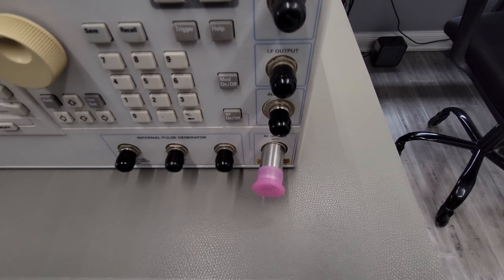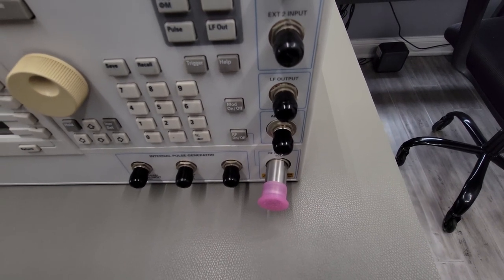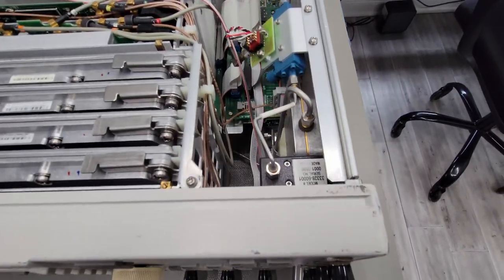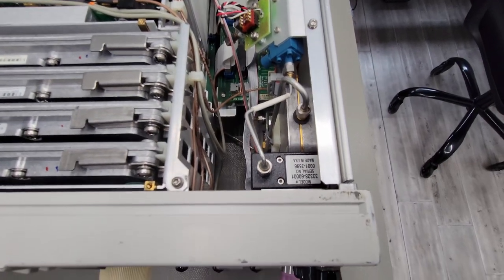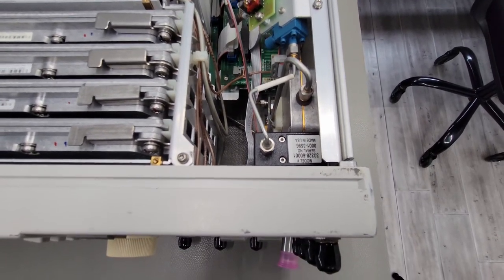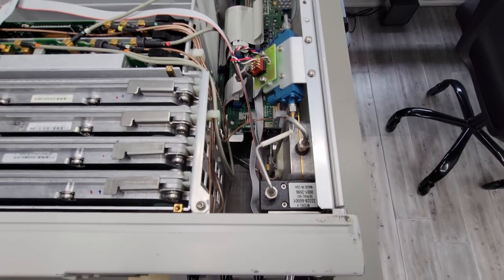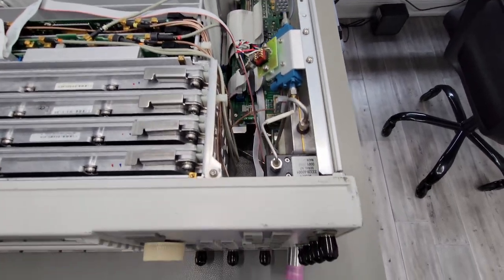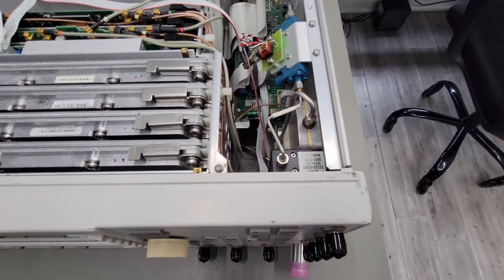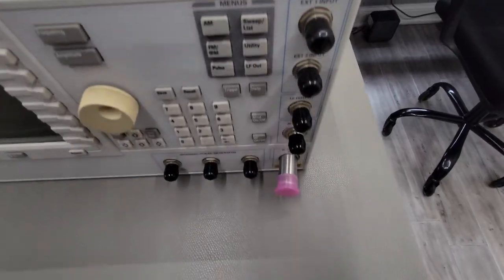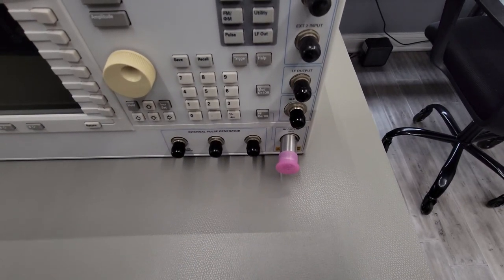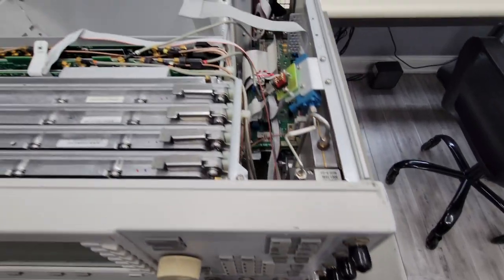So I'm going to make sure that this is not damaged, the connector itself, and then we can work our way backwards from the microwave front end, so we can test the attenuator out of the instrument and then check the levels and all the signals as we work our way back. And we'll see if indeed that low amplitude symptom we're seeing is a result of this or something else going on internally.